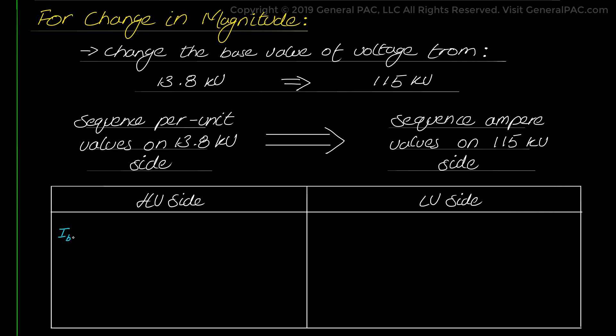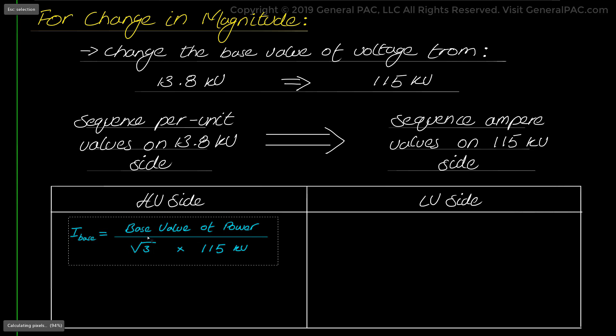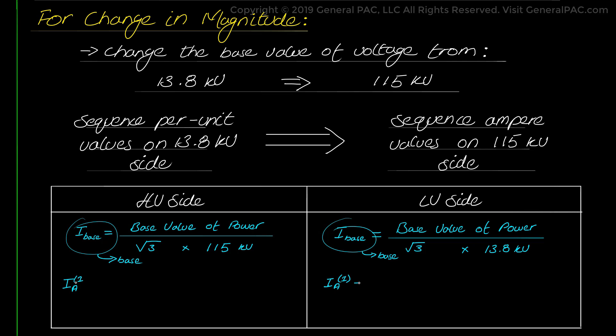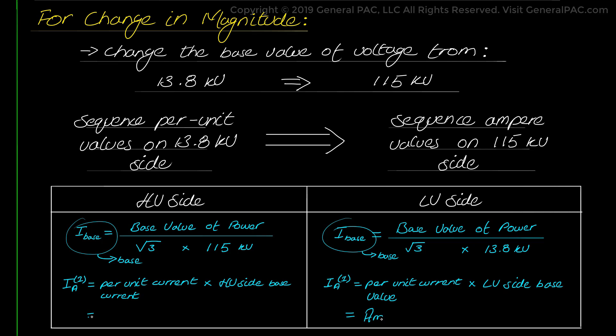On the high voltage side, the base current equals the base value of power divided by the square root of 3 times 115 kV, giving the base current on the high voltage side. On the low voltage side, we take the base value of power and divide by the square root of 3 times 13.8 kV, giving the base current for the low voltage side. For both sides, we calculate the ampere values by multiplying the per unit current by the appropriate base, using the right formulas to get either the high voltage or low voltage current in amperes.